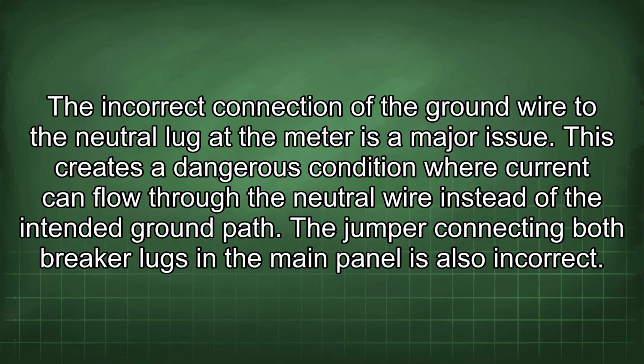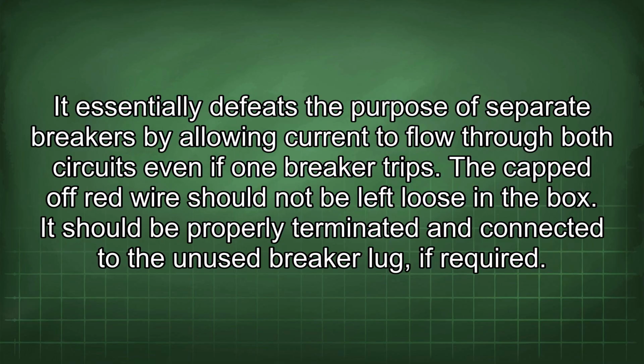The jumper connecting both breaker lugs in the main panel is also incorrect. It essentially defeats the purpose of separate breakers by allowing current to flow through both circuits even if one breaker trips. The capped-off red wire should not be left loose in the box. It should be properly terminated and connected to the unused breaker lug if required.